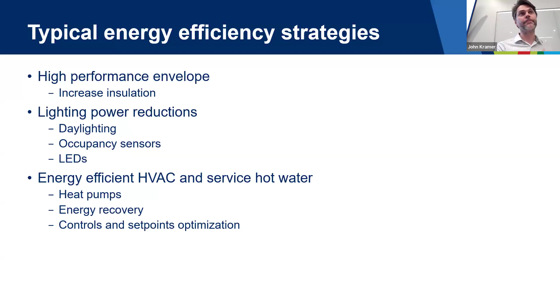That's just looking at the energy part. When you add in embodied carbon, things get much more complex because they don't necessarily align. For instance, improving operational carbon by adding insulation might be bad from an embodied carbon perspective. So you have to optimize the insulation choice. From an embodied carbon perspective, you might want something low impact like mineral wool, even if it performs worse thermally, whereas for operational carbon you might want continuous insulation or spray foam, which has a high embodied carbon impact.